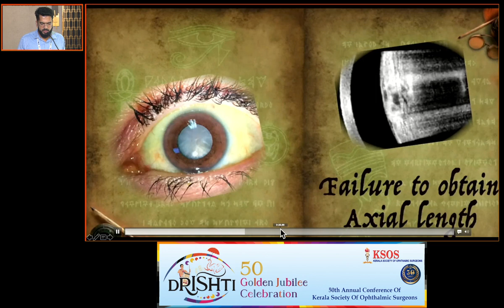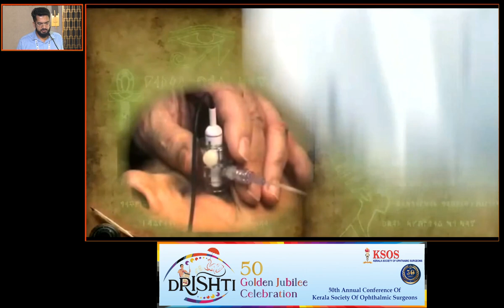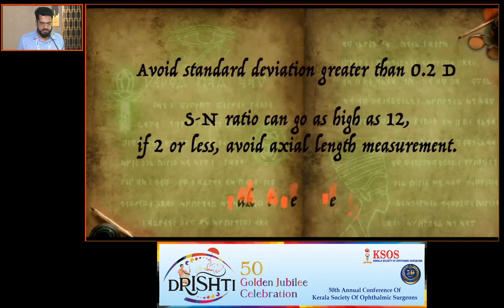Here the main thing is that errors occur in calculating the axial lengths, and we have to make sure that we are not using the older methods. We may have to use the latest optical biometers, or also take up ultrasonic immersion techniques to get a good axial length. When taking the measurements, we have to check the standard deviations from the optical biometers and the signal-to-noise ratios also. We should not accept deviations of more than 0.2 diopters, or a signal-to-noise ratio of less than 2.